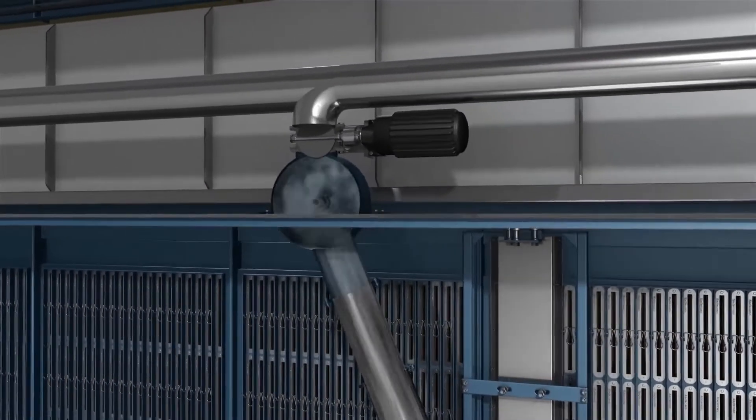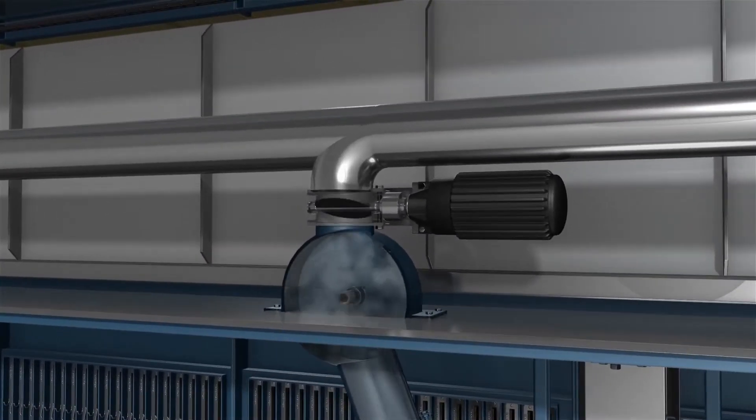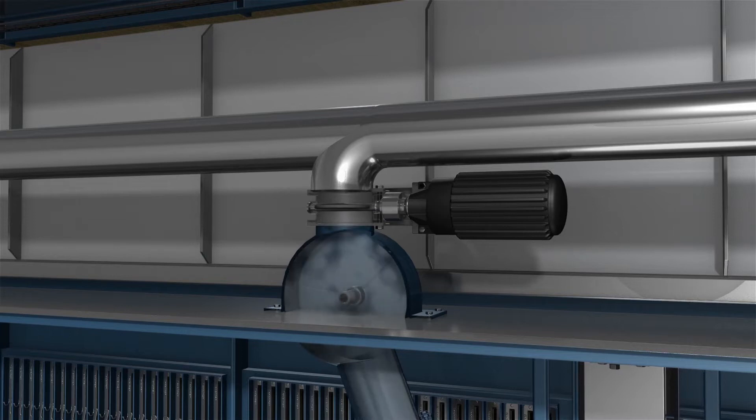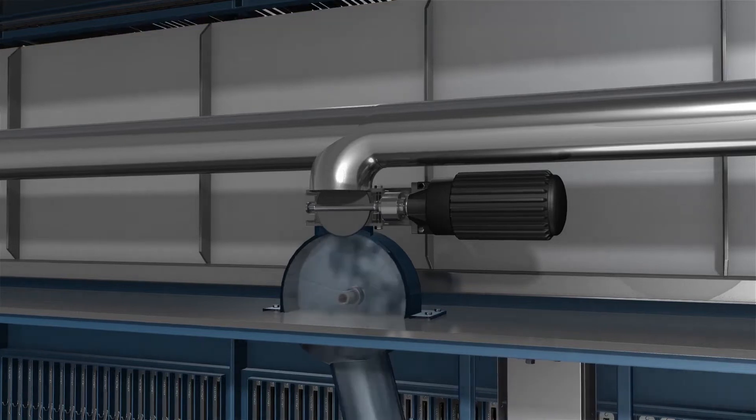The air valve, above the cleaning air radial fan, pulses air which inflates the filter bag during the cleaning cycle and creates an airflow opposite the filter direction.